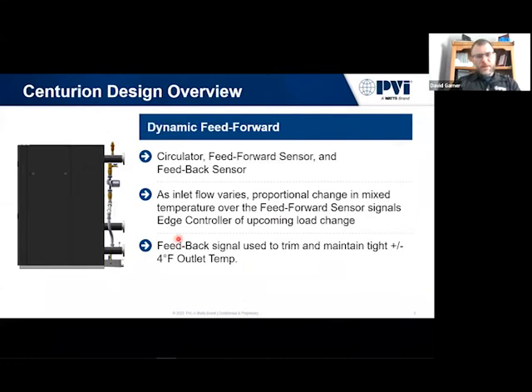When we look at the back of the unit, there's a circulator here on the back, and this is what we use for our feed forward sensor. This pump turns on intermittently, but what the unit's doing is it's looking at the temperature at the top of the heat exchanger and the bottom of the heat exchanger, and it's using that to calculate flow. When the top and the bottom of the heat exchanger are the same temperature, we know there's no flow. As we start seeing the temperature drop at the bottom, that's our way of seeing that, hey, cold water is being introduced into the system, or we're also looking at the return water temperature from the recirc line.